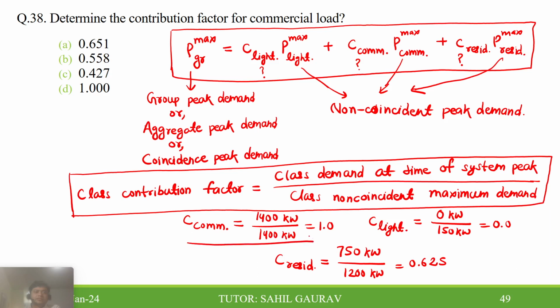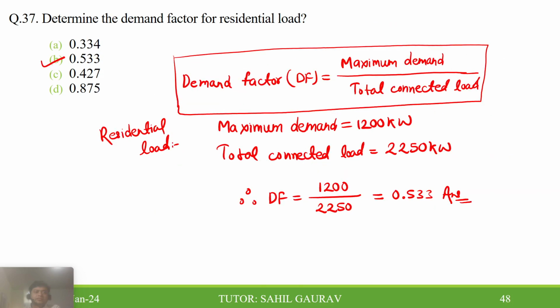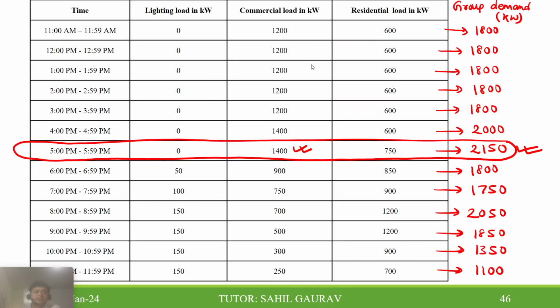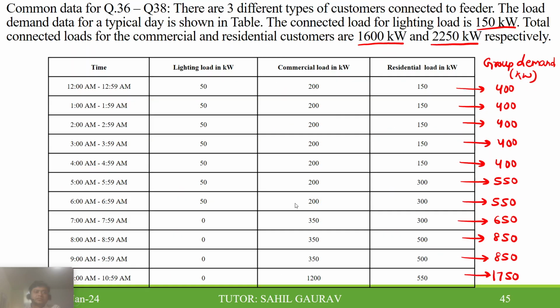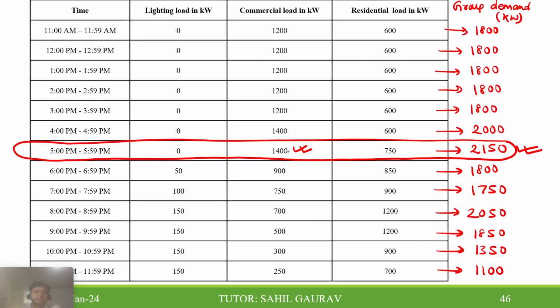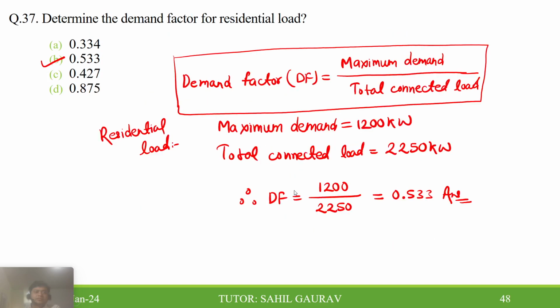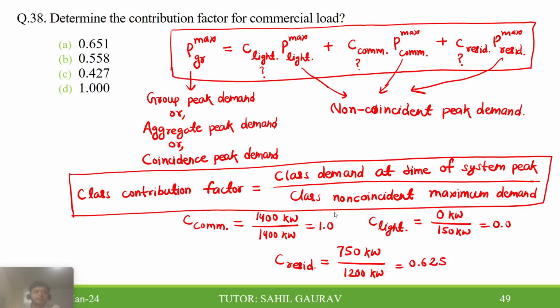So the numerator will be 1400, and then the class noncoincident maximum demand. What is the individual maximum demand for the commercial load? If you see the table, the commercial load maximum demand is coming as 1400 itself. So it is 1400 divided by 1400, and you will get the contribution factor for the commercial load as 1.0.